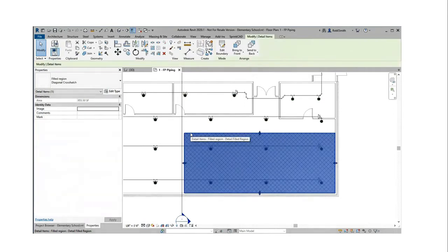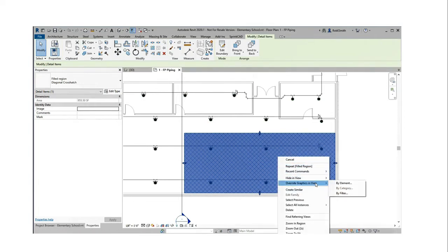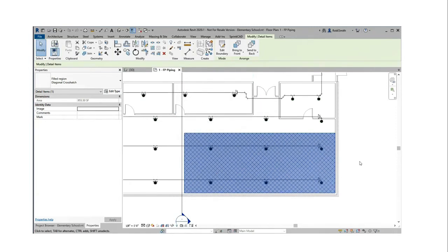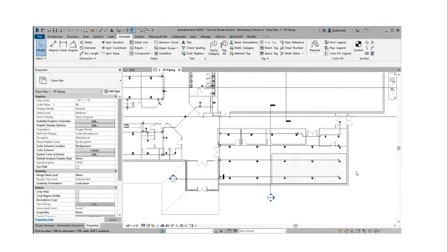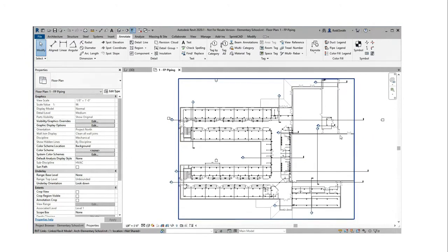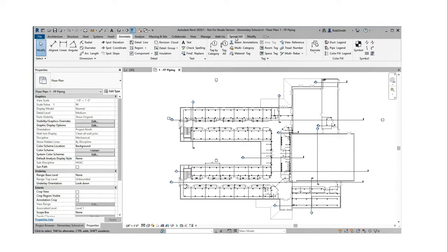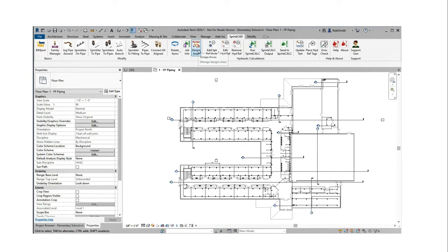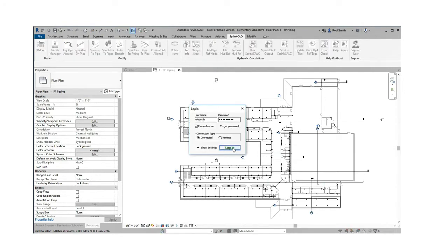Back in the SprinkCAD section I saw I needed five heads as a minimum; I've got six flowing, so this is an acceptable design area. I clicked off and everything disappeared. It took me a little while, but I figured out: if I modify the object by element and change the transparency of the region down to about 95%, I can see through the region to the heads I want. If there's a better way, send me an email — I'm a real beginner at Revit. Now I can see the heads I want and I'll zoom back out to create a design area.